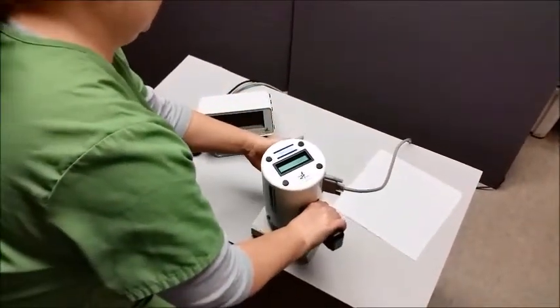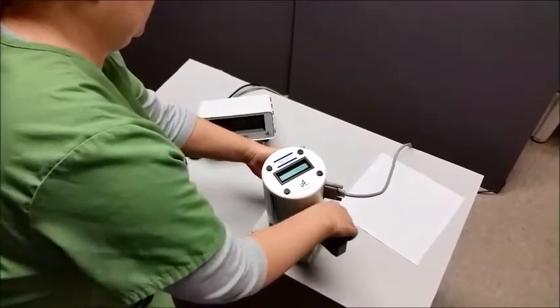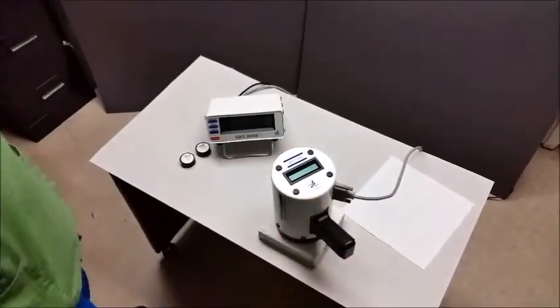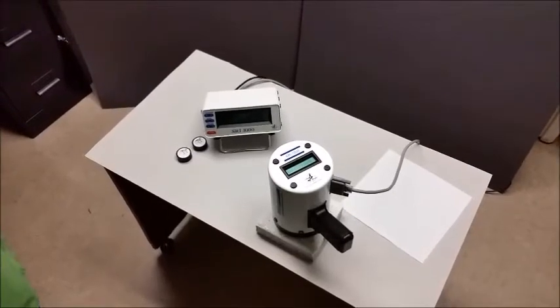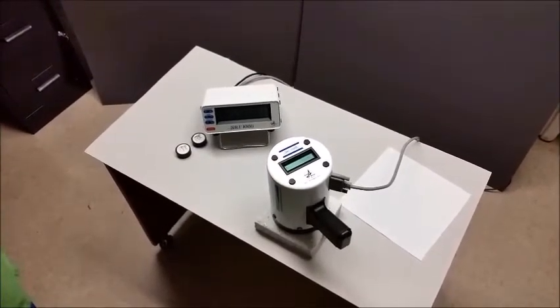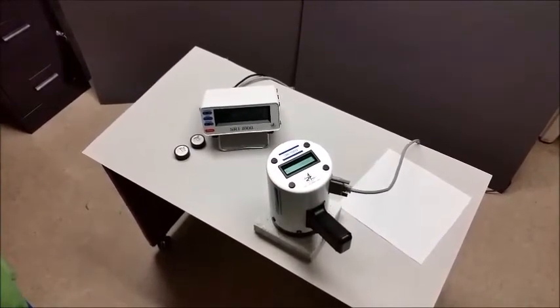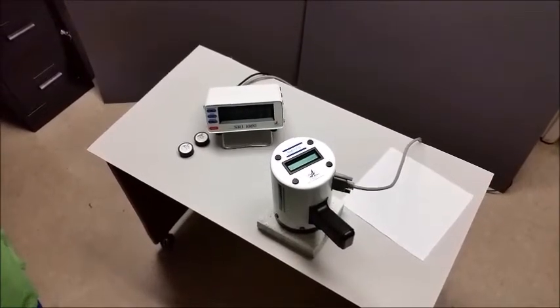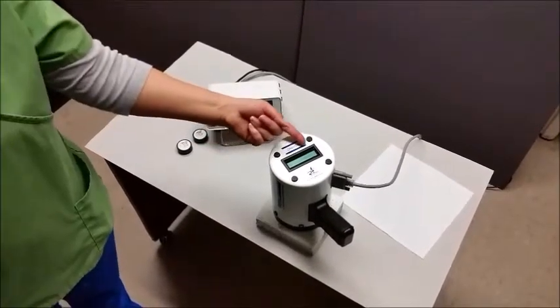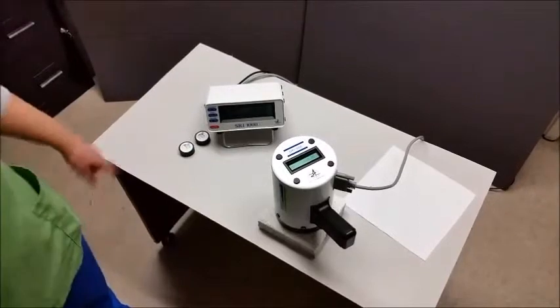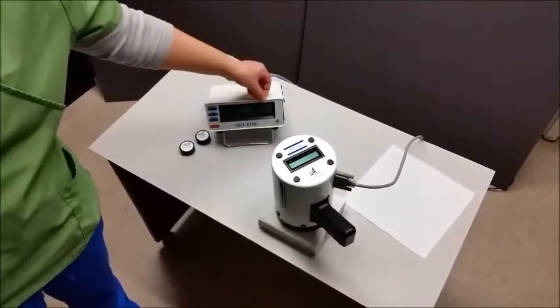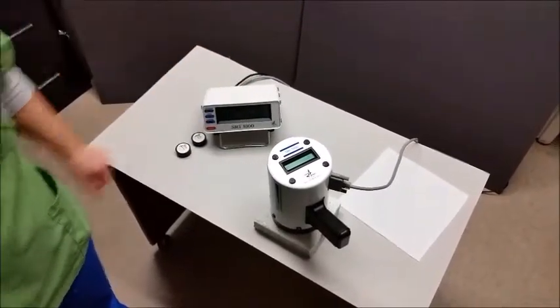Carefully pick up the instrument head, turn it upside down, such that the aperture port will set directly on top of the sample, making sure the head is firmly placed on the sample. With the measurement head in this position, you will be able to see the measurement readings on the measurement head as well as on the control display unit.